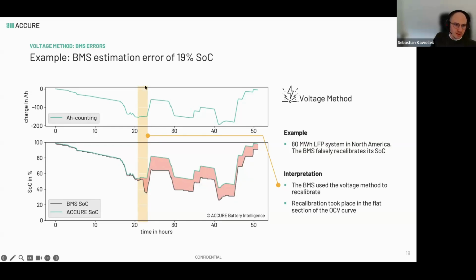At a certain point, the BMS will basically recalibrate. So up until here, everything was pretty fine. You have the SOC, there's a minor deviation, you're just going through the hours, and here at hour 21 or so, the system recalibrates because it thinks it's somewhere else, and then you create this significant offset that you pull through the whole system until you end up at a very high SOC again. That's something you want to avoid.